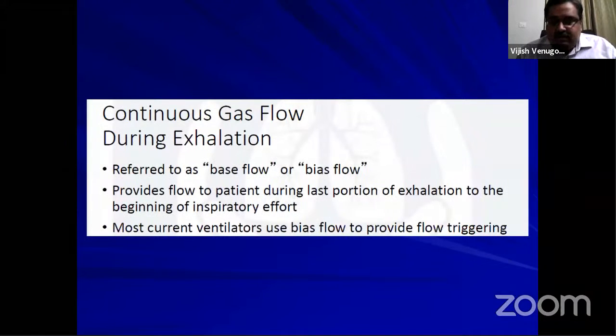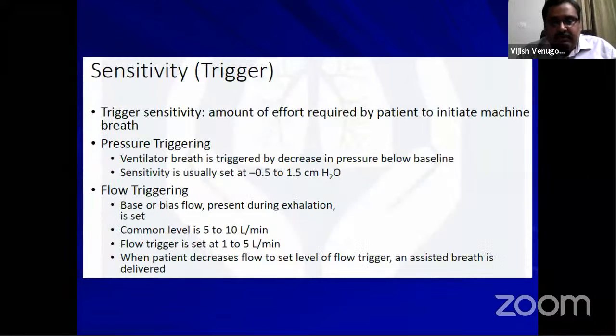So this is again telling something about the base flow, and this base or bias flow, which is happening immediately after the exhalation till the next inhalation, is the one which provides for flow triggering. Now, this very important component, trigger sensitivity, is the amount of effort required by the patient to initiate a machine breath. So again, it's just a repetition. In pressure triggering, the sensitivity we usually set from 0.5 to 2 centimeters of water, both negative. And in flow triggering, we usually set at a value of around 2 liters per minute.